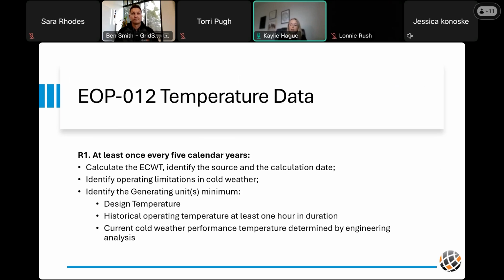You'll want to identify your operating limitations in cold weather and your generating unit's minimums. We'll look at your design temperature, the minimum the unit was built for; the historical operating temperature, the coldest it's ever run for at least 1 hour; and the current performance temperature, performed during an engineering analysis, reflecting the unit's present capabilities.